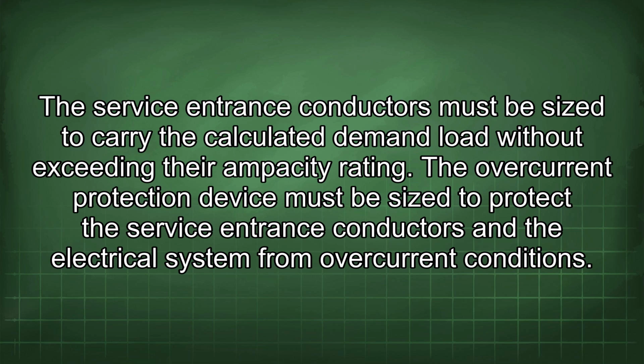The service entrance conductors must be sized to carry the calculated demand load without exceeding their ampacity rating. The overcurrent protection device must be sized to protect the service entrance conductors and the electrical system from overcurrent conditions.